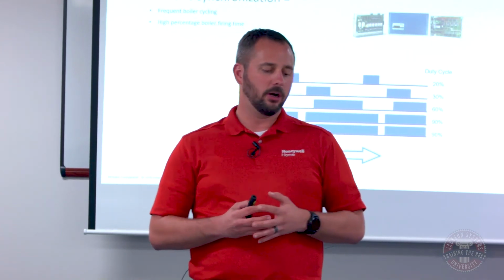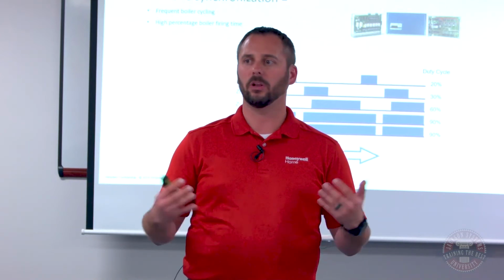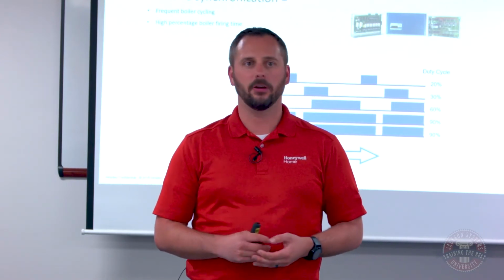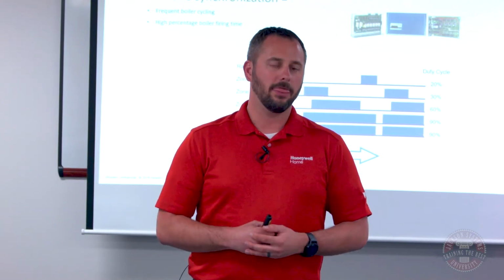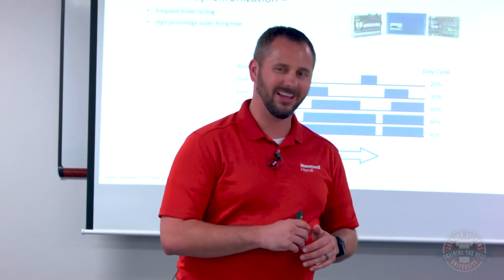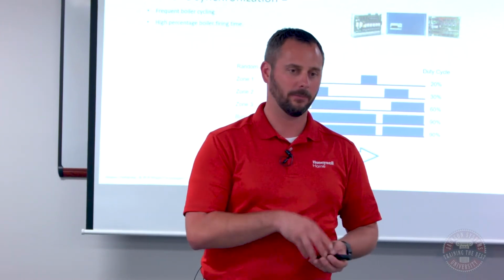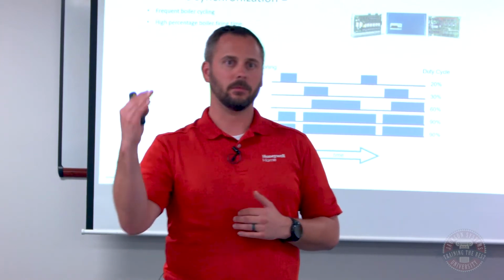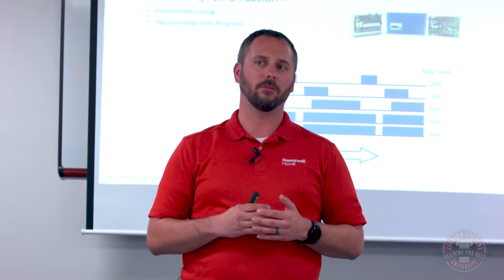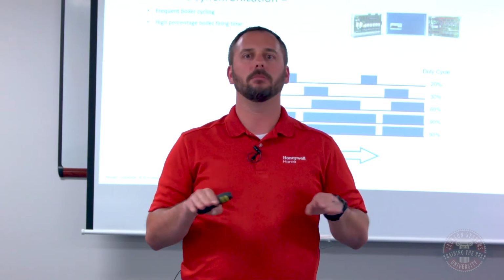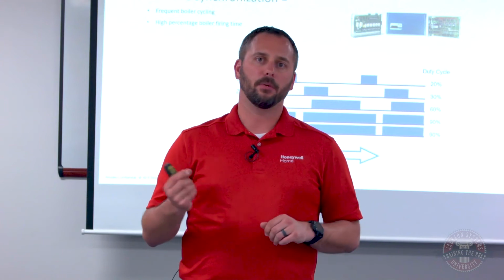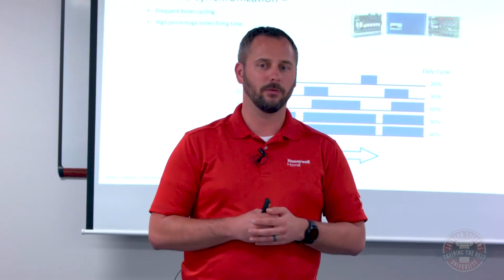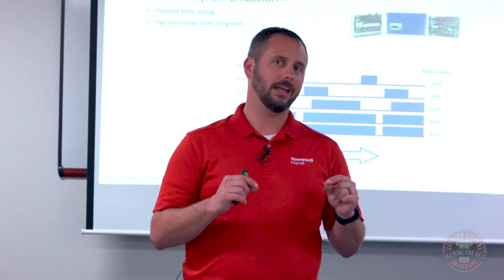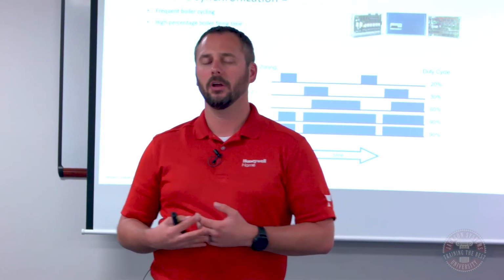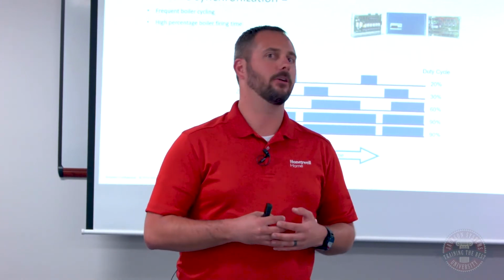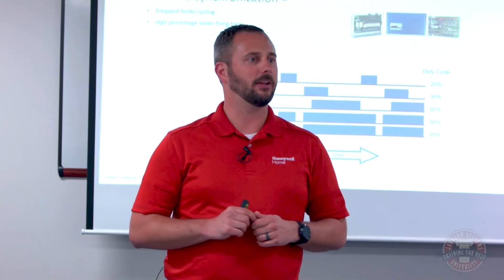So I've got a couple of slides up here. In a typical hydronic heating system, because we love zoned hydronic heating systems, I've been in houses that are 2,000 square feet that have like 15 zones in them. That's a little excessive. Let's say we've got, even with today's modulating and condensing boilers, a 100,000 BTU boiler. If that boiler modulates, say it's got a 5-to-1 turndown ratio, the minimum firing rate is 20,000 BTUs. Sounds very small. The problem is if you put 15 zones in a 2,000 square foot house, some of those zones, in the worst case scenario, design day conditions, only need 800 BTUs, 900 BTUs, and it's very rare that all thermostats are calling for heat at the same time.